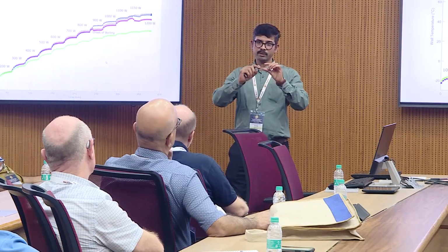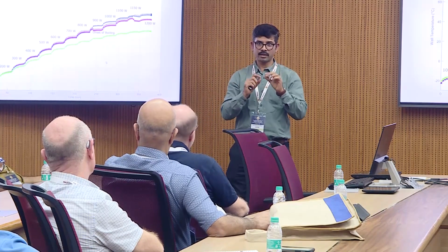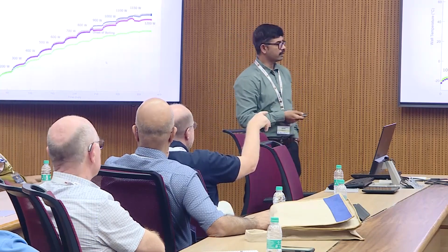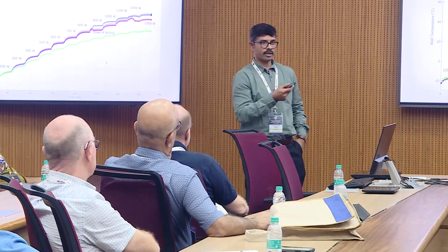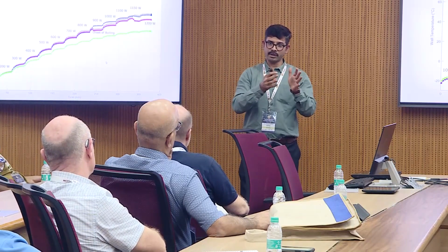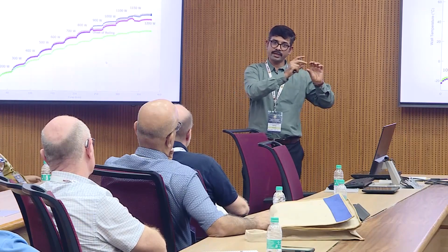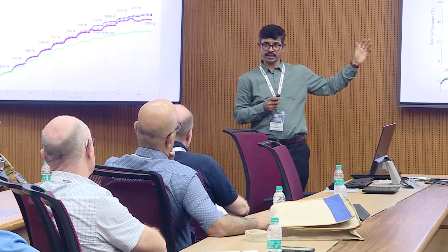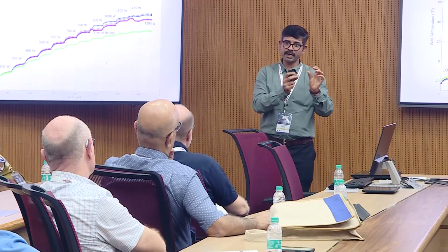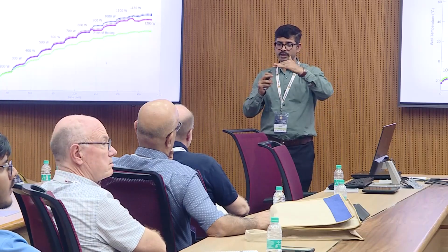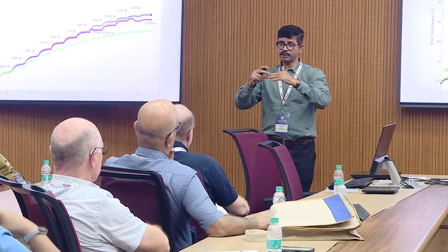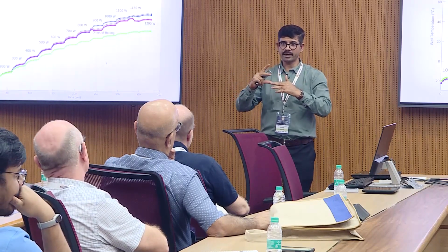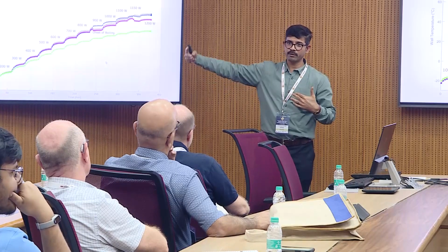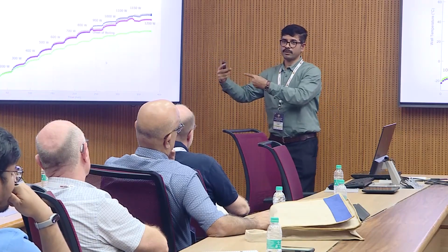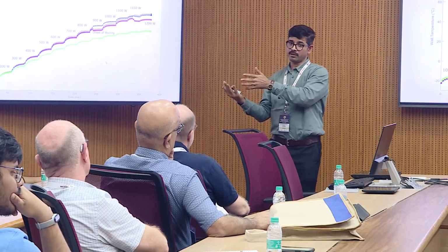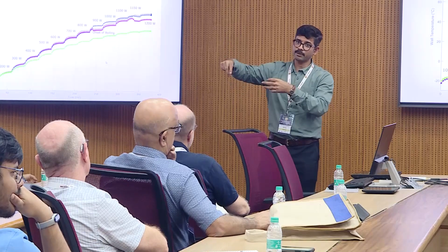You're talking about the delta T between the evaporator and the condenser? Yes. The green line is the condenser. Actually, the delta T at the evaporator is uniform. If you see the single phase zone of the MPFL, the delta T at the evaporator is slightly higher. Once the two phase boiling starts, the evaporator is at a uniform temperature. But the delta T between evaporator and condenser will be slightly higher because the condenser will be in the subcooled zone, meaning it will be a separate zone, where it is releasing latent heat of evaporation and coming back as a subcooled liquid.